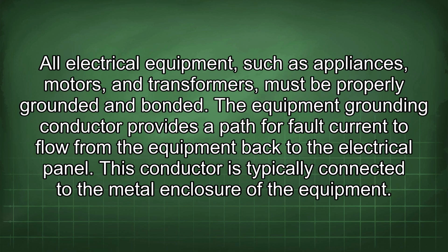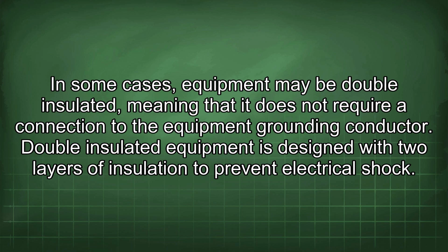All electrical equipment, such as appliances, motors, and transformers, must be properly grounded and bonded. The equipment grounding conductor provides a path for fault current to flow from the equipment back to the electrical panel. This conductor is typically connected to the metal enclosure of the equipment. In some cases, the equipment may be double insulated, meaning that it does not require a connection to the equipment grounding conductor. Double insulated equipment is designed with 2 layers of insulation to prevent electrical shock.